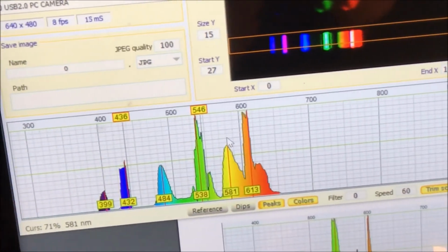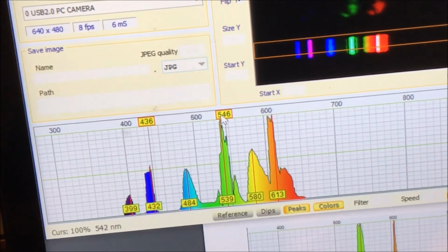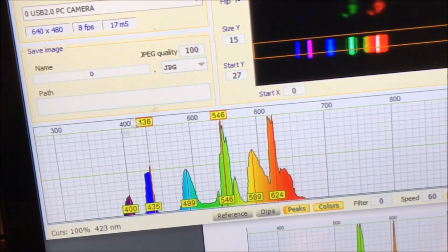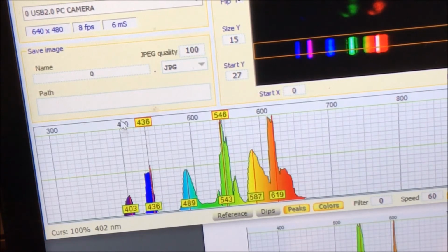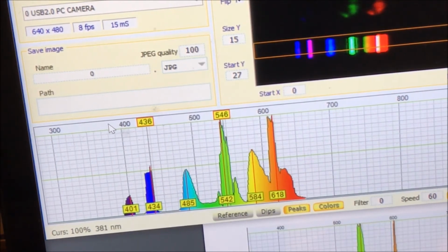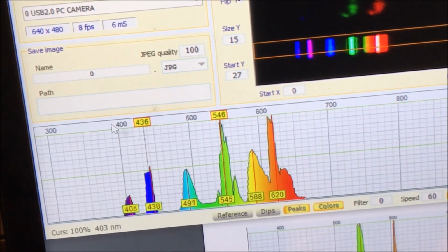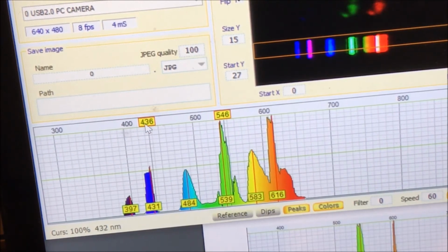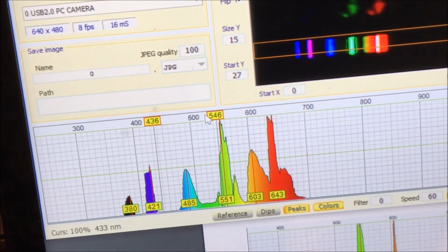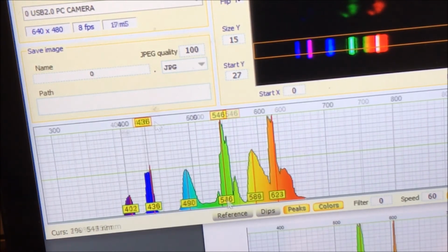Okay, so let's try to calibrate this in. We can move our 546 over to the left, and this one just a bit over. The controls here are a bit strange. If you grab the axis or if you grab the yellow box, they do different things as far as stretching the whole thing or just moving it left to right. You can see the automatically generated maximum point value adjusting. So there we have it, 436 to 436, 546 to 546. Perfect. So now this is calibrated.